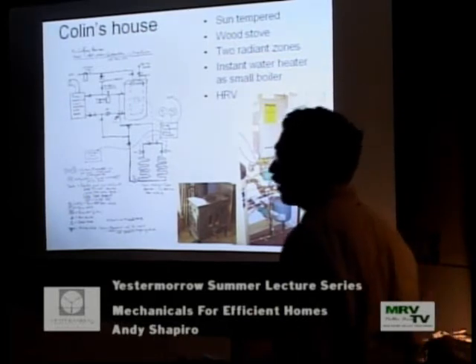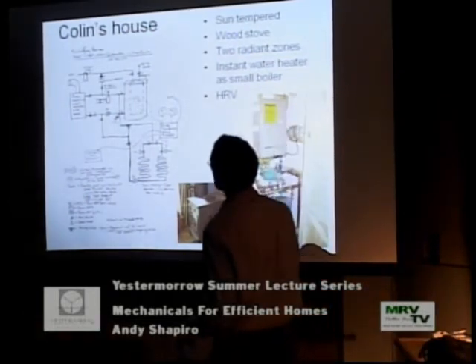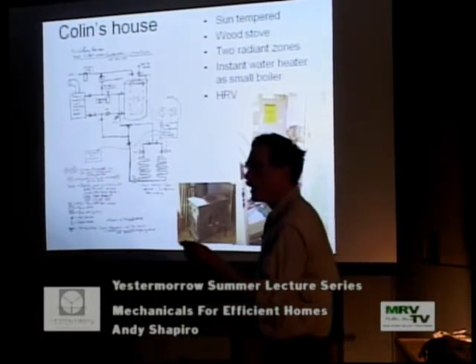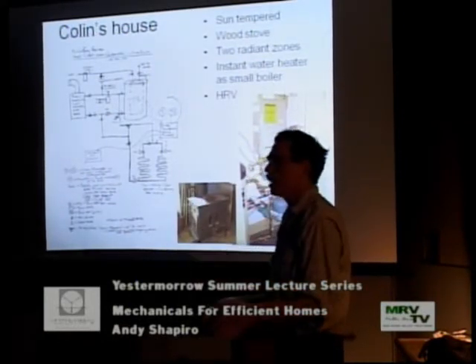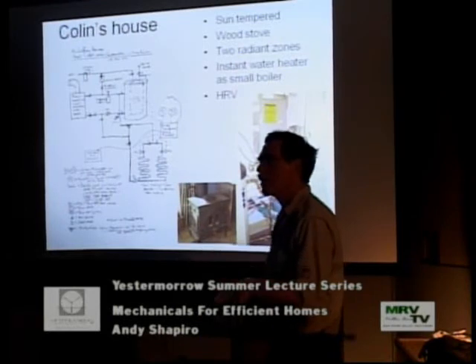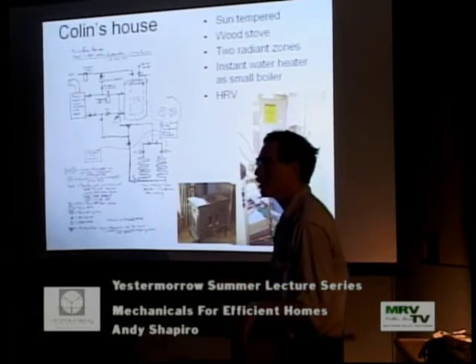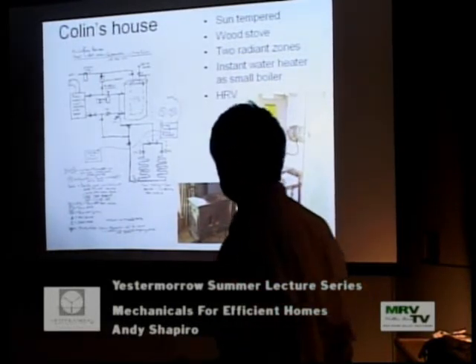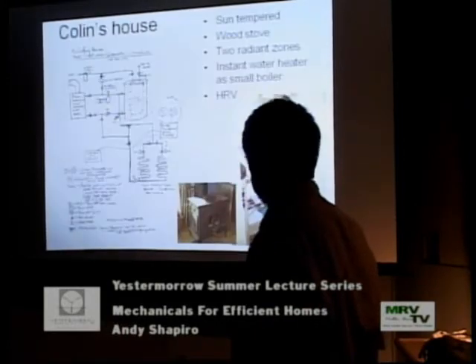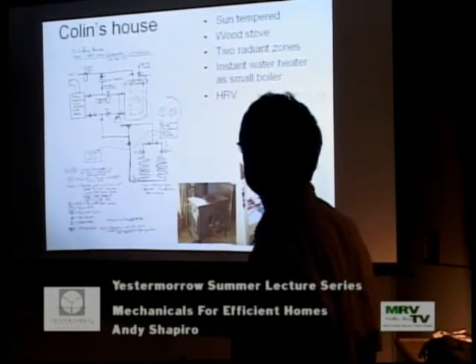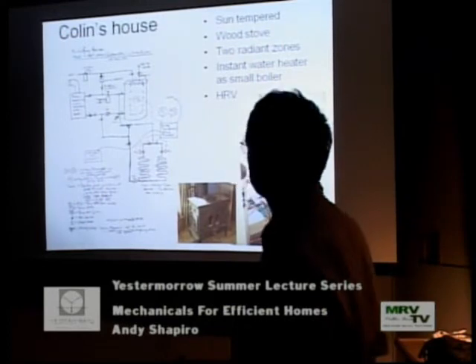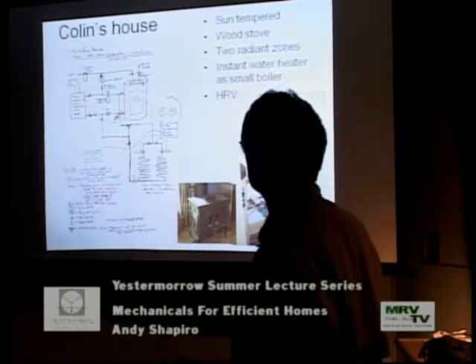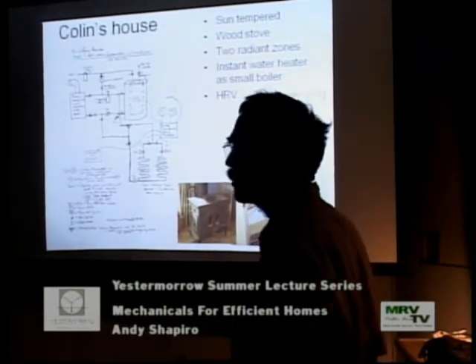In terms of hard water, the inside tank is very thin metal, and it's wrinkled like this. So as it expands and contracts, it knocks off the scale down at the bottom. It's a pretty cool system. The nice thing here is we're able to use this instantaneous water heater with hard water, because the only thing it's looking at is captive water in here, we're not running water through it all the time.